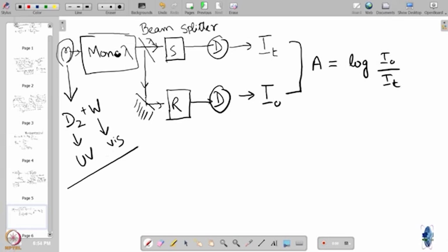In some spectrophotometers, they also use xenon lamp, but it is not very popular because first of all, xenon lamp is more costly, more intense, and in an absorbance kind of experiment you do not want an intense lamp, because what you are recording is a difference, right. If it is too intense, the difference will not be too much. So, deuterium and tungsten combination is the most popular choice for absorption spectrophotometer.